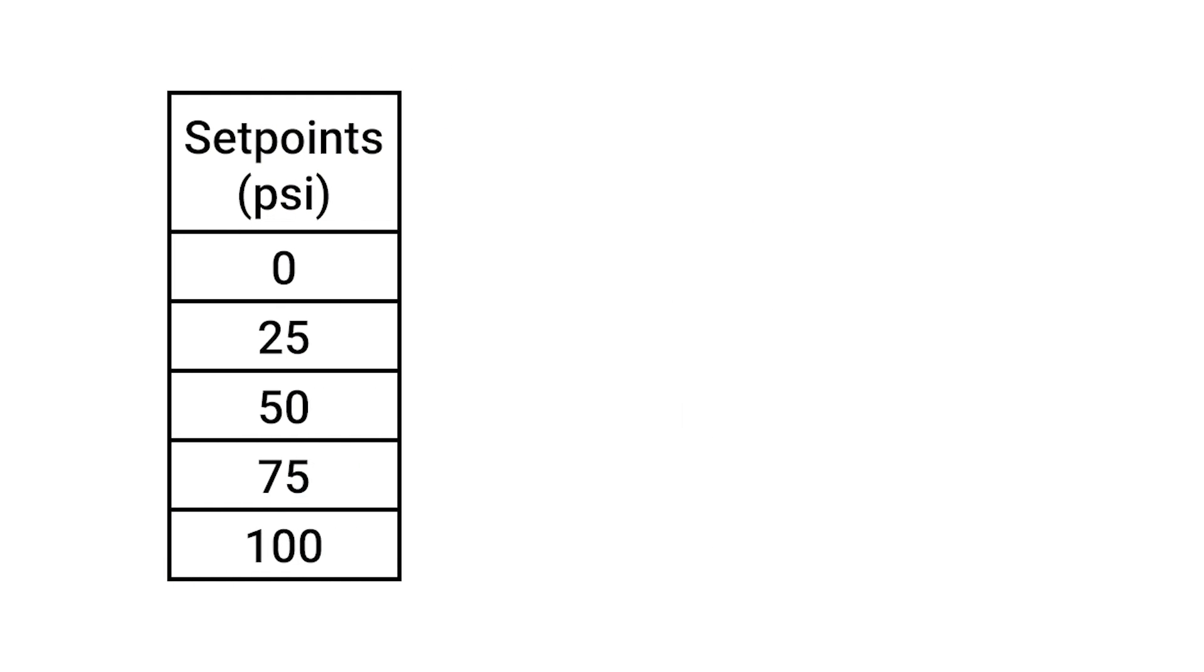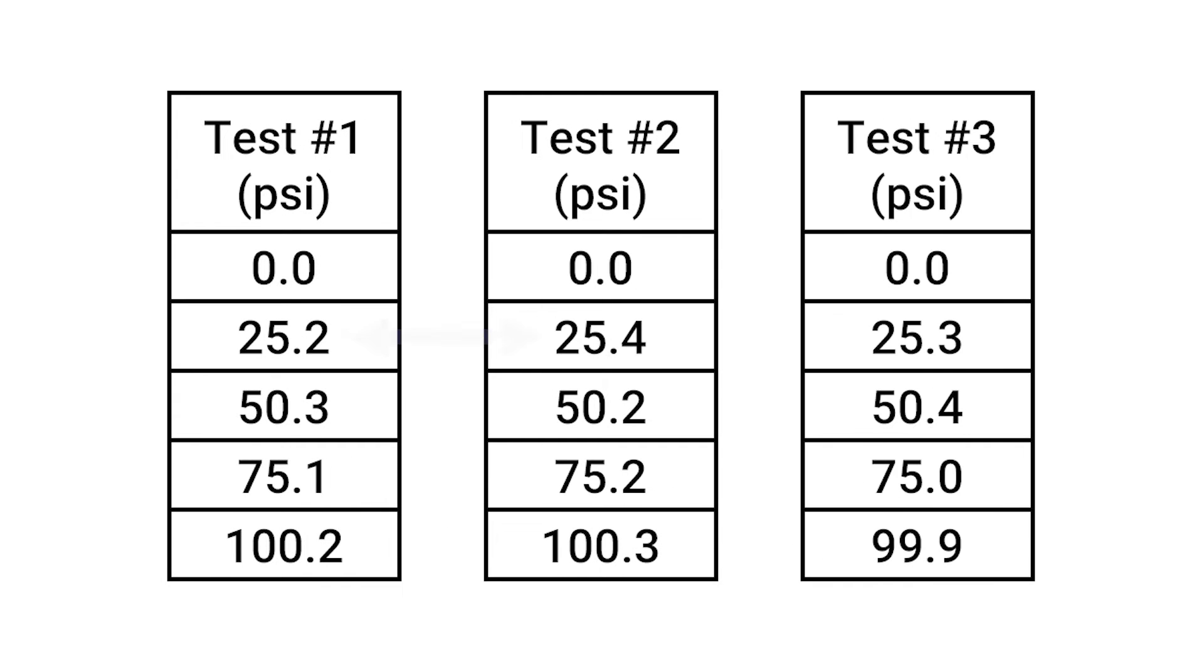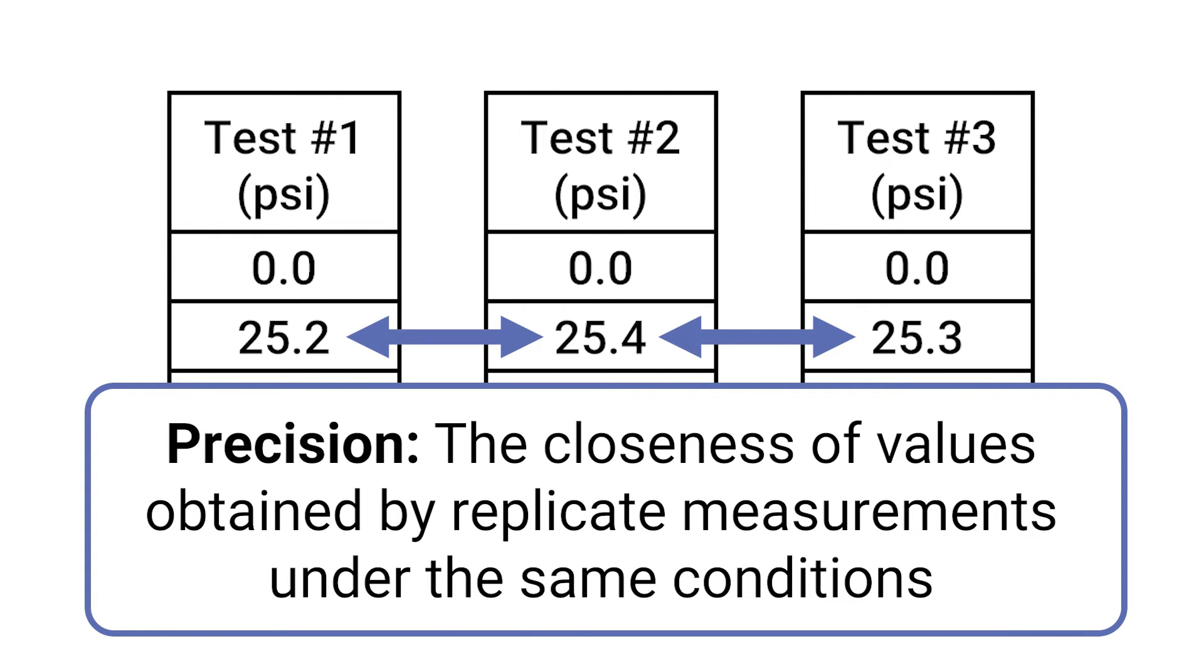If a measurement set point is taken multiple times under the same conditions, for example if this test was cycled up and down multiple times, the difference between recordings from the same set points is referred to as the precision of a measurement.